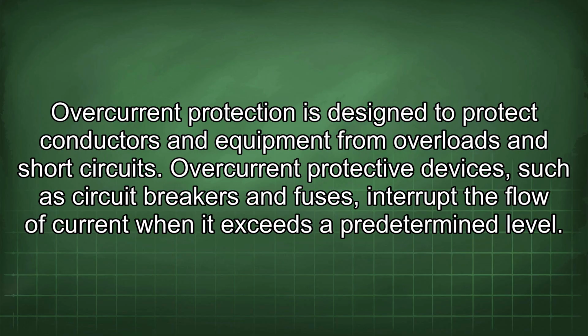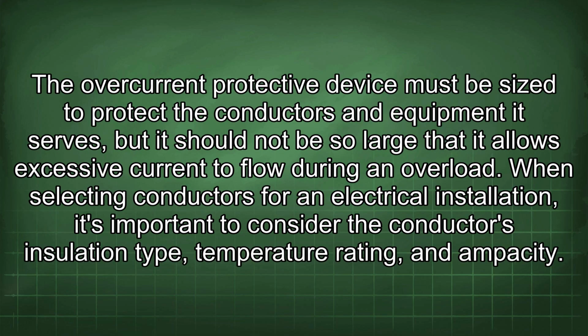Overcurrent protection is designed to protect conductors and equipment from overloads and short circuits. Overcurrent protective devices, such as circuit breakers and fuses, interrupt the flow of current when it exceeds a predetermined level. The overcurrent protective device must be sized to protect the conductors and equipment it serves, but it should not be so large that it allows excessive current to flow during an overload.